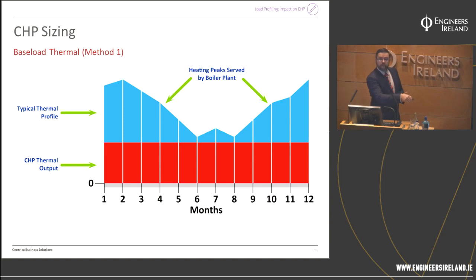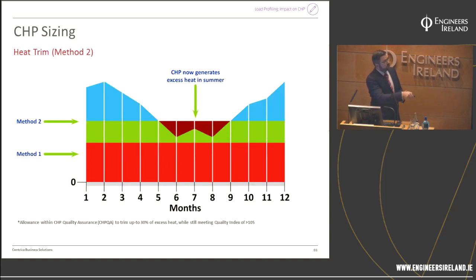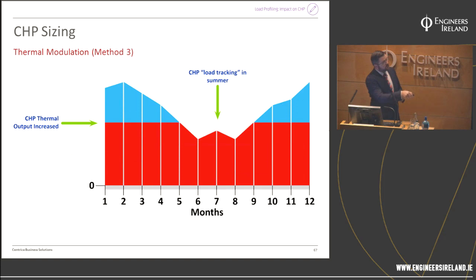So we keep that as a backup plan. Because if we end up with the CHP here, and if it cuts out, the CHP will have to cool down before it can come back on again. That's where people have fallen into a trap if they expect the CHP to map like a boiler would.